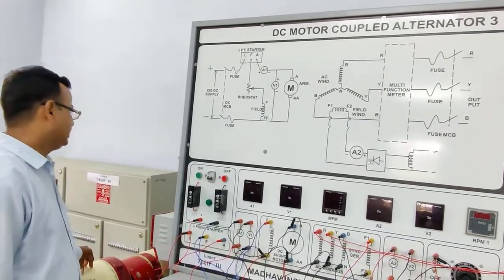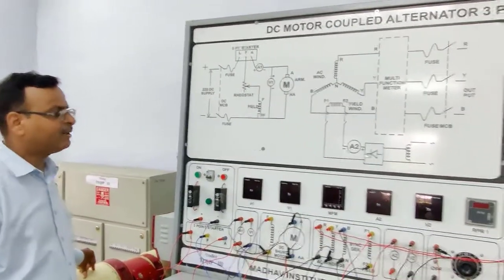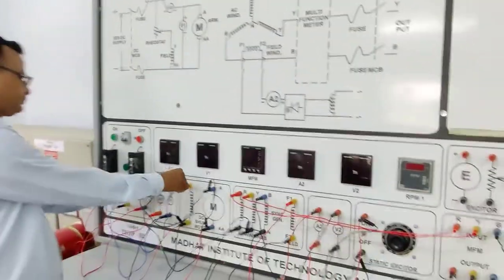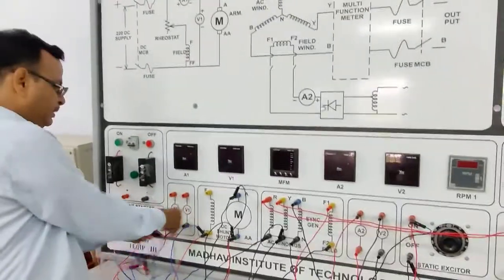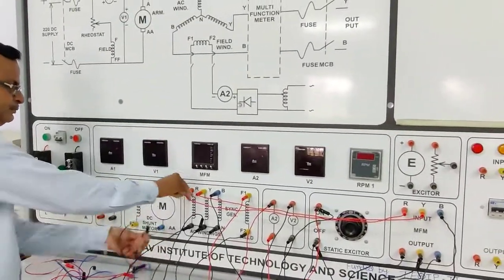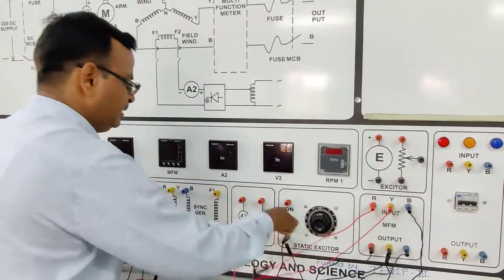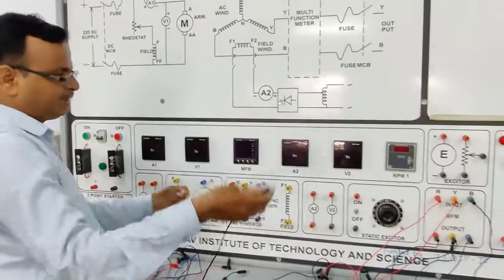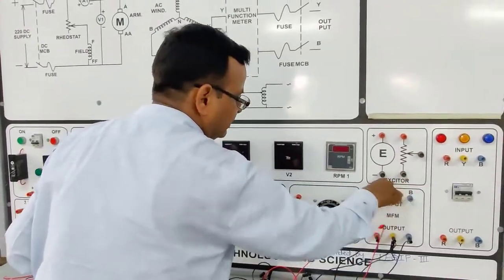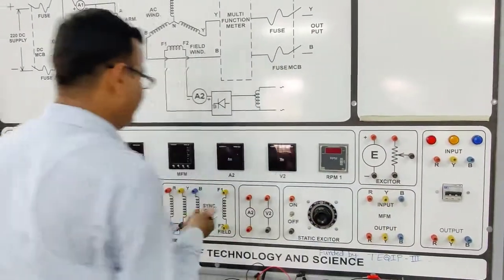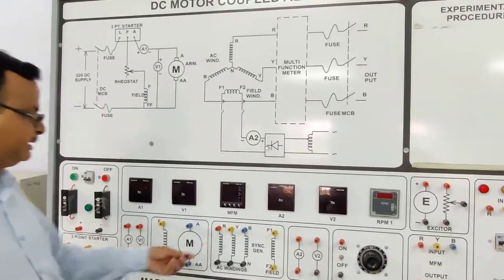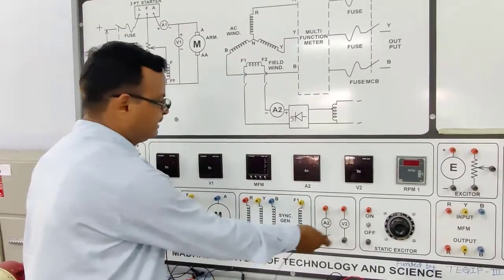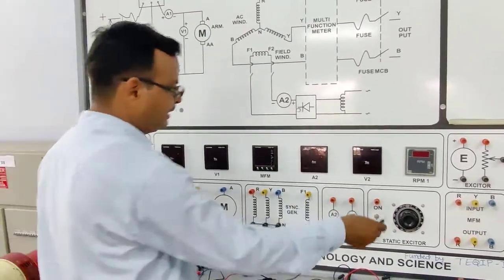The next test is also necessary for finding the stator winding resistance. The stator winding resistance means remove all the terminals, and we will calculate the stator winding resistance. How to calculate the stator winding resistance? Simple, we can calculate using Ohm's law. These are stator winding terminals, these are internally connected, so we keep the DC supply across any 2 phase like this.